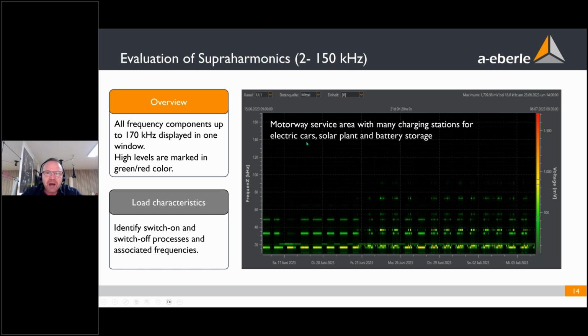Here we see a nice carpet coming out of the software, and here we analyze all the disturbances of all harmonics and supraharmonics over a time period of 21 days. During the 21 days at this area, they install more and more batteries and electric chargers. Black means there's no interference, no disturbances in our measurement data. And the color moves from green to yellow to red. This is the height of the disturbances.